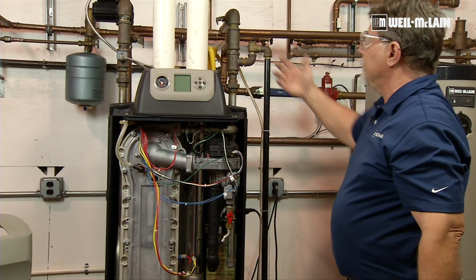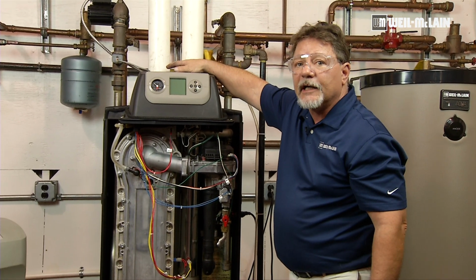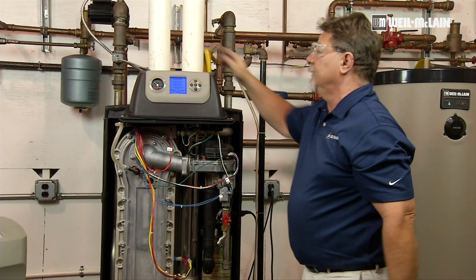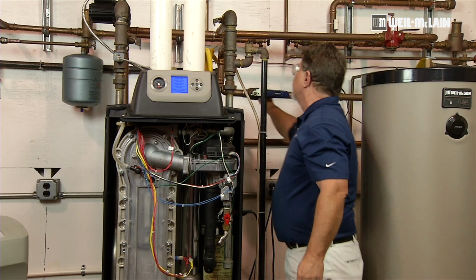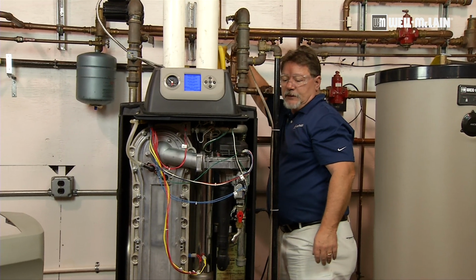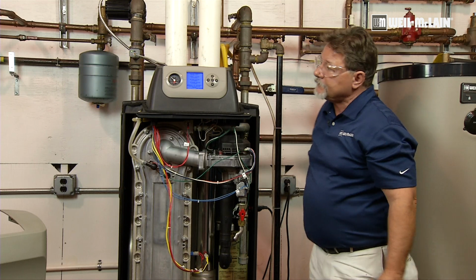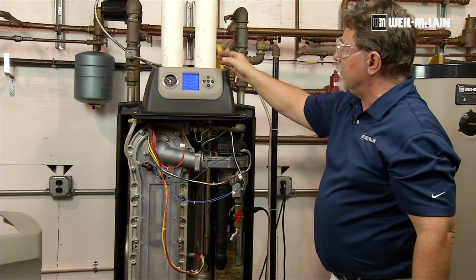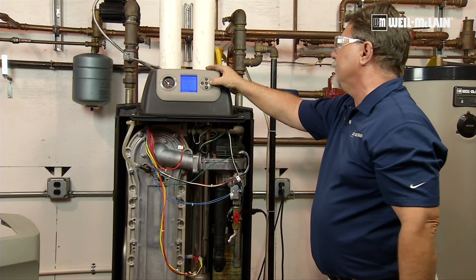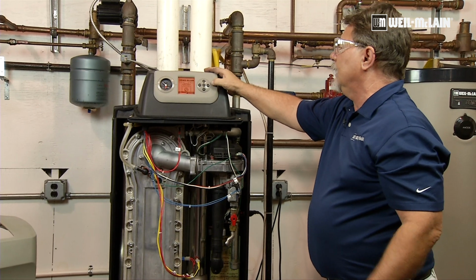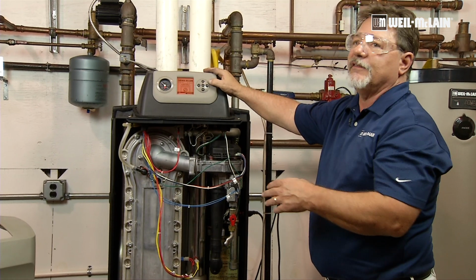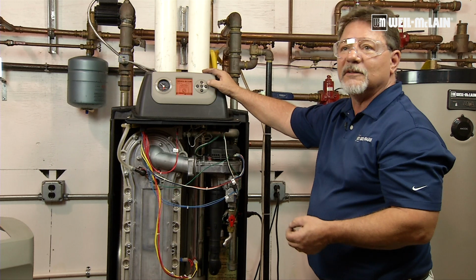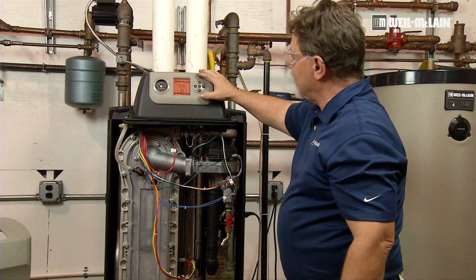So at this point, we're going to turn the boiler back on electrically, and we're going to open the gas connection to the boiler. After it goes through its loading menu, we want to reset our maintenance reminder, and that's why the screen is red.